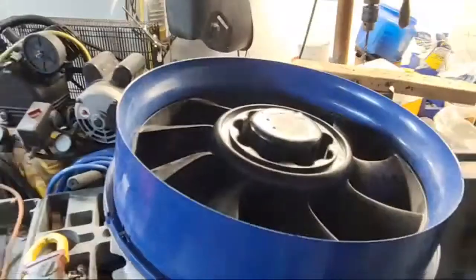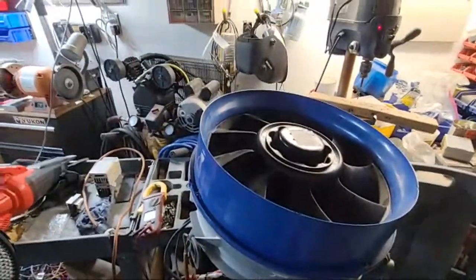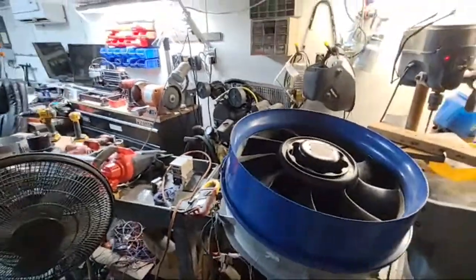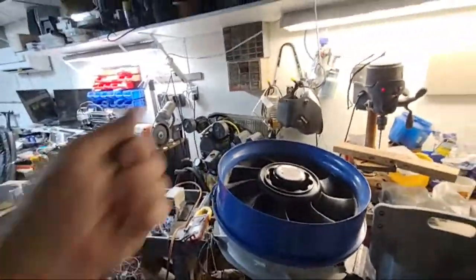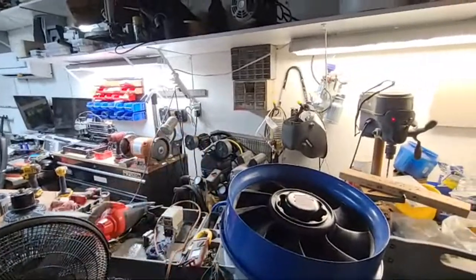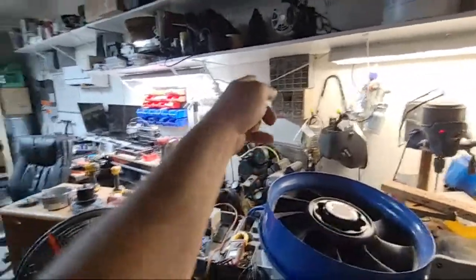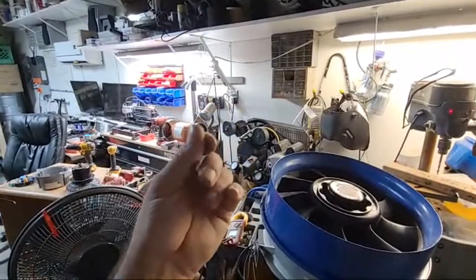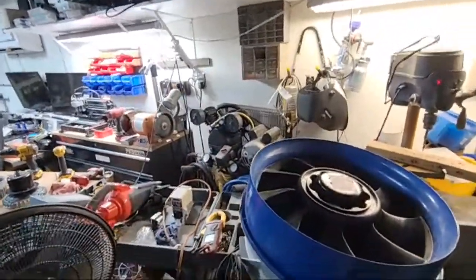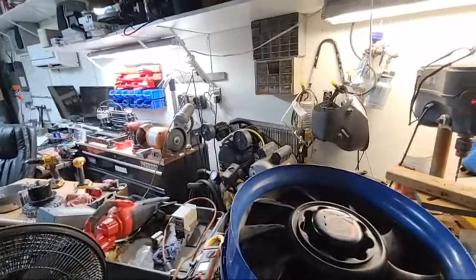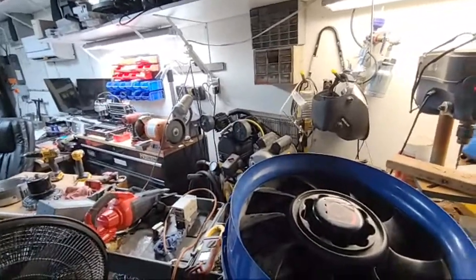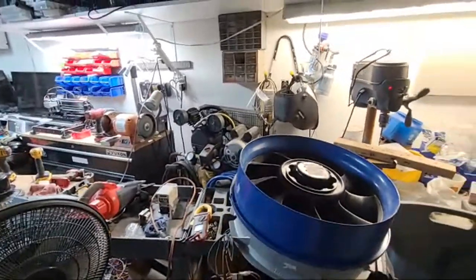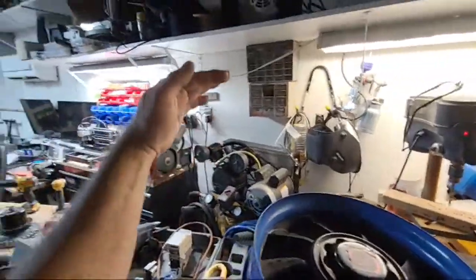If you've ever plugged in a regular ECM - I have a bunch of them in that stack over there - you plug a cord into a 120 volt furnace or air handler in an attic or wall that has an ECM, and it goes pow. If you keep doing it, let the capacitors discharge and plug it in again, it'll melt the end of your plug, because it's instant, could be 100 amps, 200 amps, whatever your circuit can handle, for milliseconds or microseconds before the capacitors charge up and it drops.